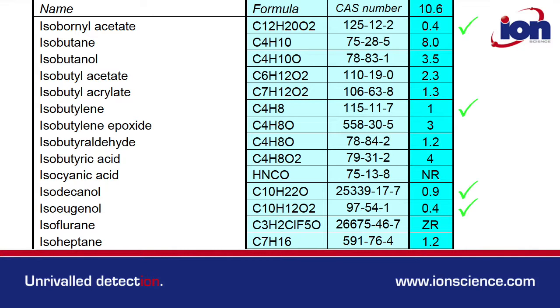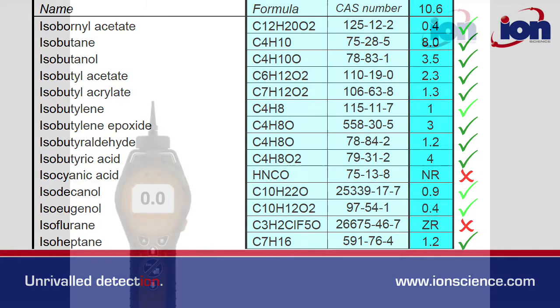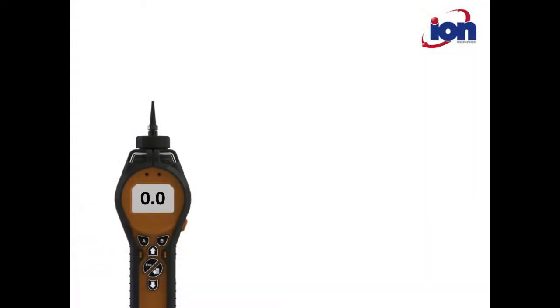Compared to isobutylene, gases with response factors lower than one are more detectable, and gases with higher response factors are less so. Some VOCs are undetectable.